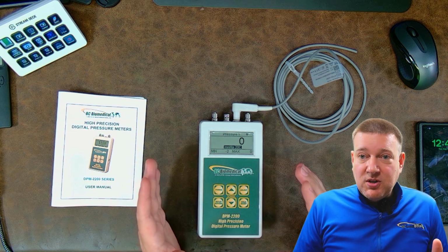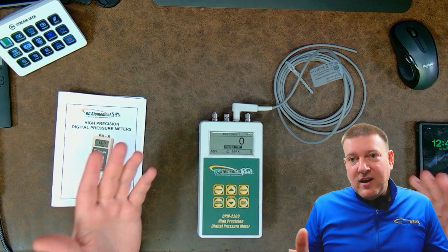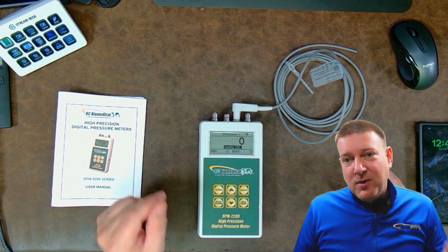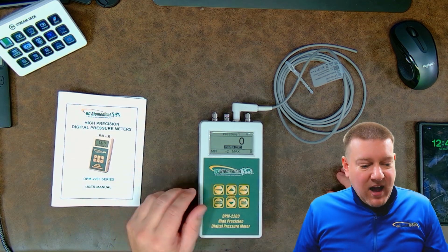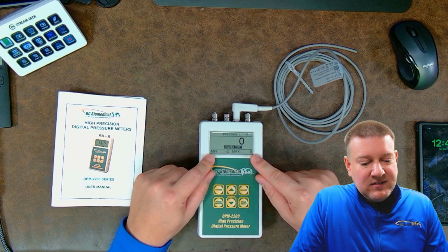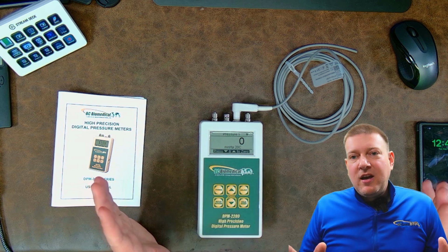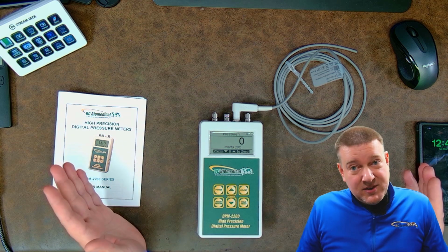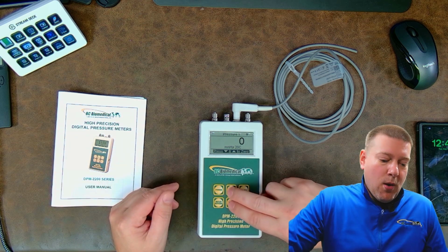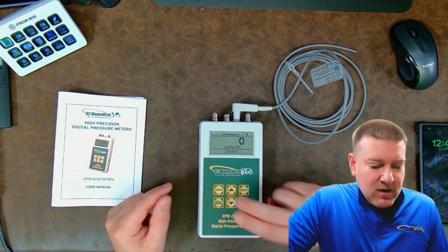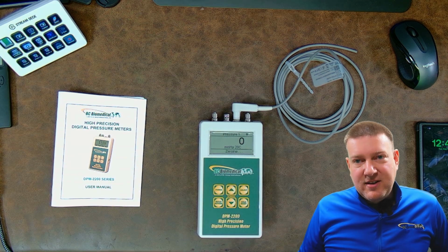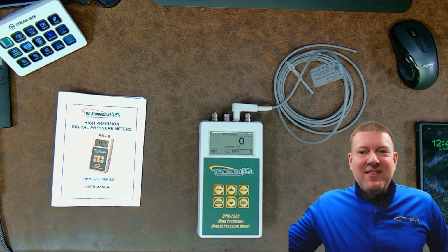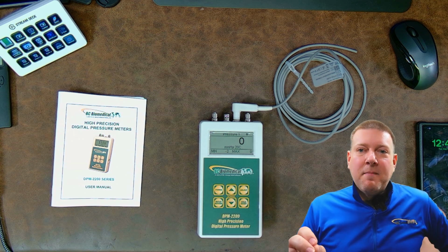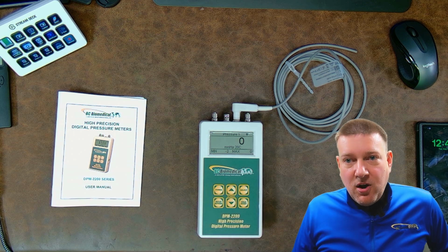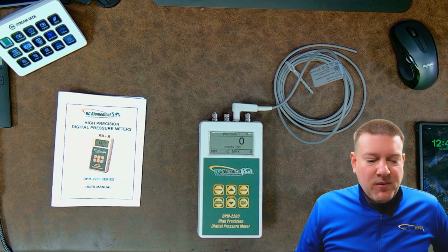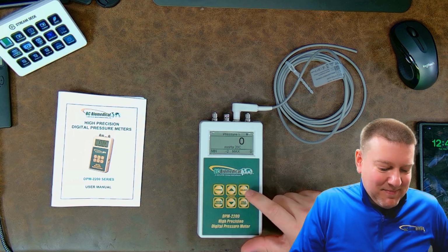Since this is a precision instrument, it's got both of those ranges, because in engineering terms the temperature differential of mercury is going to matter, and these guys have made allotments for that. Notice down here at the bottom it says min and max, and we can go through those. Let's say you want to zero the pressure meter. When you boot this thing up, it zeroes itself automatically to atmospheric pressure. However, if you want to reset it yet again, you press the up and down, and it zeroes itself digitally. No more tweaking little pots. Those days are gone, and so are the days of sitting there monitoring the pressure and watching it creep up, because analog pots do allow for creep, especially if they get older. Digital ones are much more accurate.